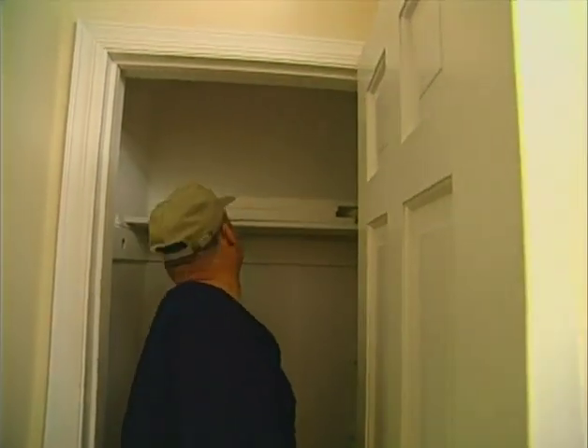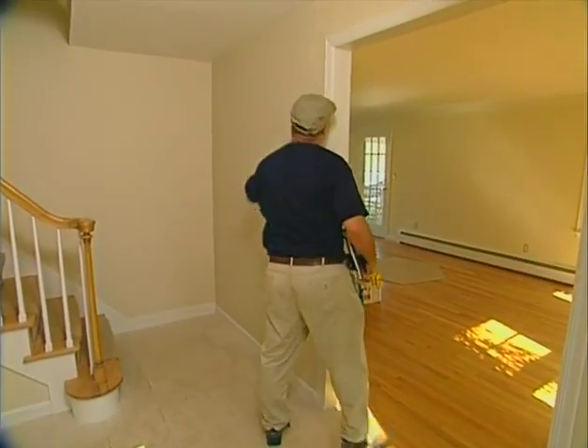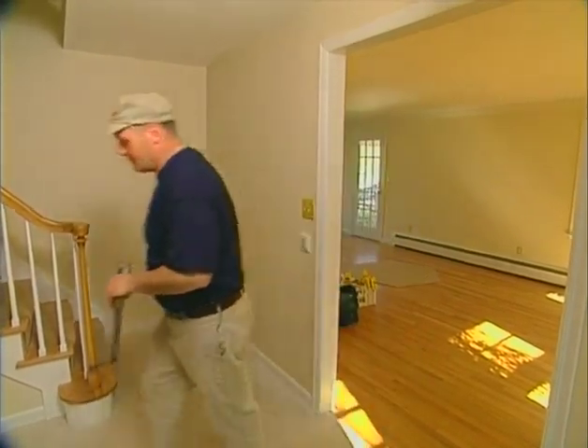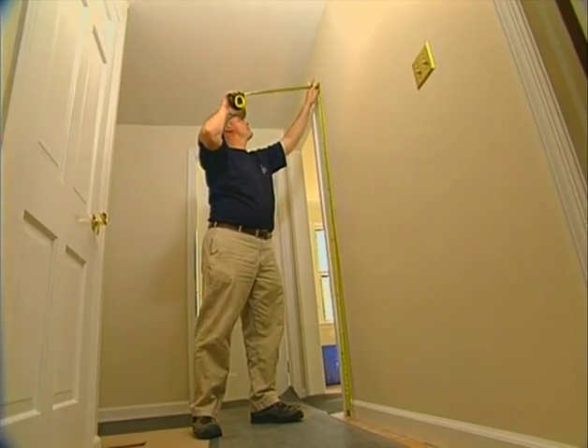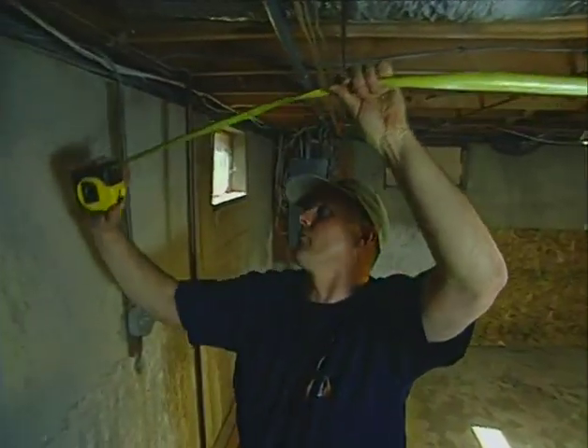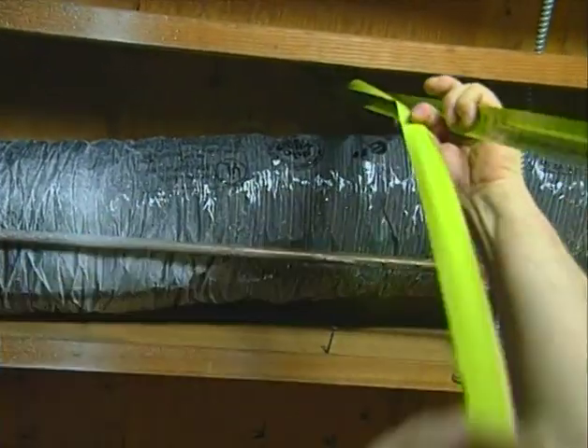Look at the house to see where people have visual contact when they walk into rooms. If they're walking into a living room, you want to avoid keeping piping or things on the opposite side of the living room where they're going to see it right away. You might want to leave it on the side where you'd walk in. But you could look for areas where you can go into wall channels and try to get the most bang for your buck. If you could use a wall channel and actually pipe 2 or 3 sprinkler heads from it, that's great because then you've created the least amount of demolition and reconstruction work in the future.